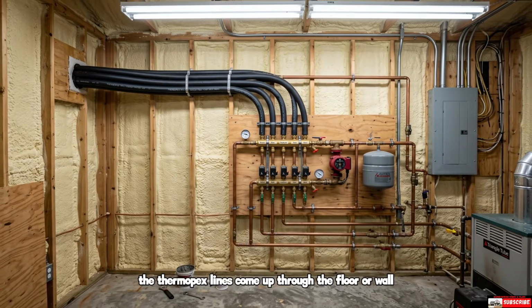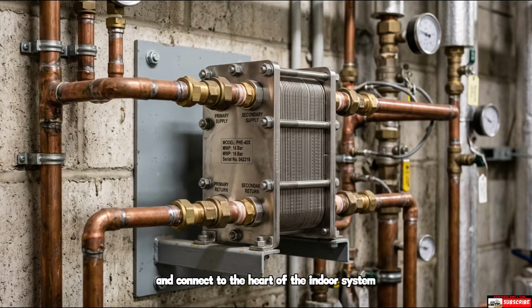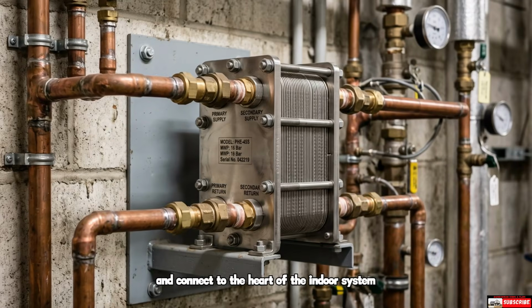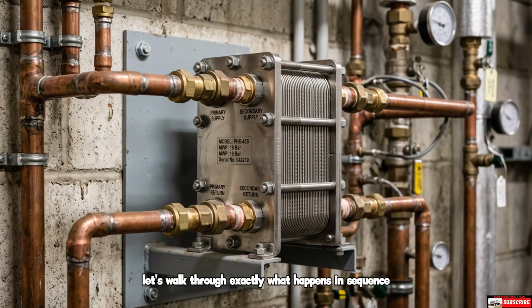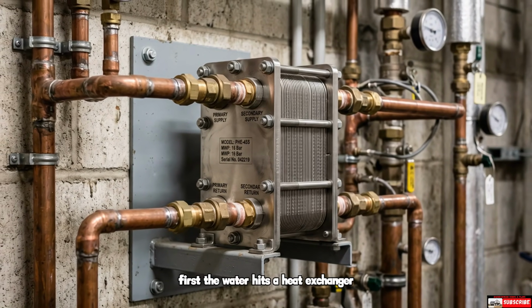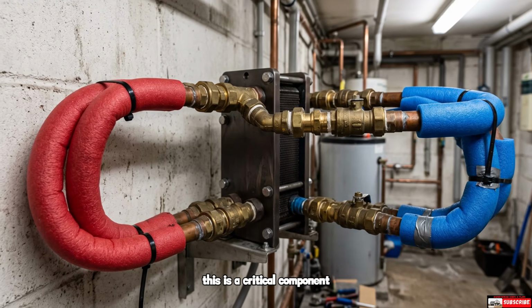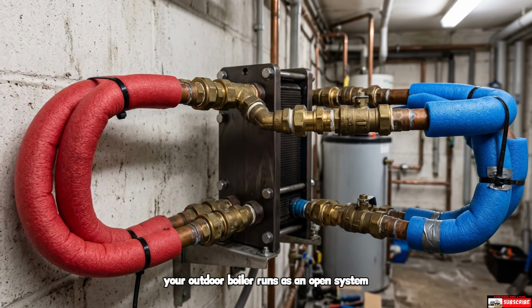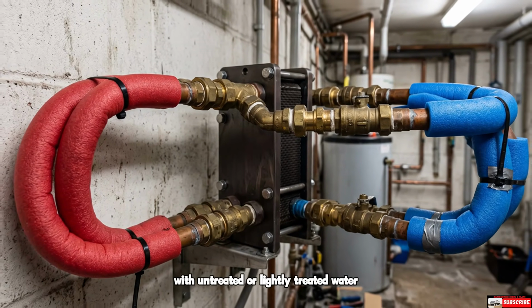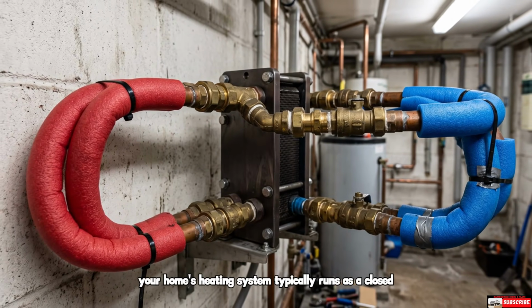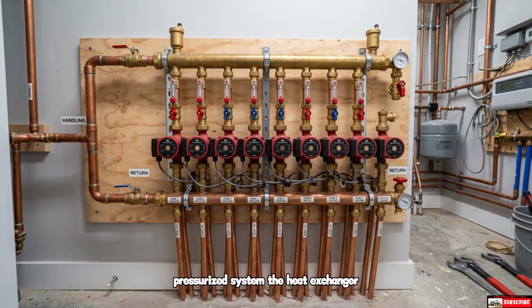The ThermoPEX lines come up through the floor or wall and connect to the heart of the indoor system. Let's walk through exactly what happens in sequence. First, the water hits a heat exchanger. This is a critical component. Your outdoor boiler runs as an open system with untreated or lightly treated water. Your home's heating system typically runs as a closed, pressurized system.